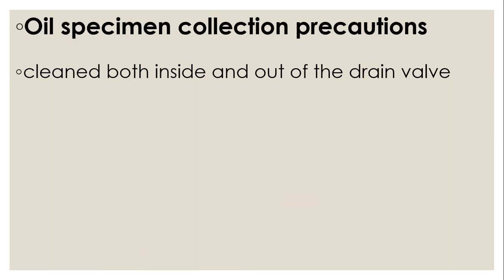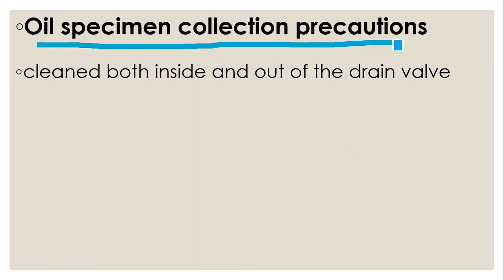Now, while collecting, the technician will be collecting oil from the transformer. You may be working in a substation or power station, and for the test, you have to collect the oil from the transformer regularly. You have to clean inside and outside the drain valve, because the drain valve is available outside generally in the yard, and it will already have a lot of dust particles. You have to clean it before taking the oil. The drain valve should be properly cleaned.